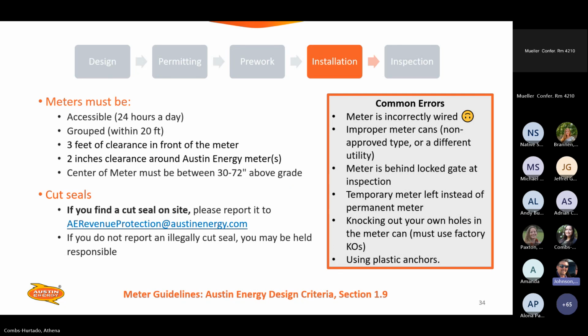So in our criteria, it does state that when running conduits into the meter enclosure, run the conduit into the factory punched knockouts only. Do not cut any holes in the meter enclosure. If holes are cut in the meter enclosure, AE will consider it damaged and will not approve the installation.